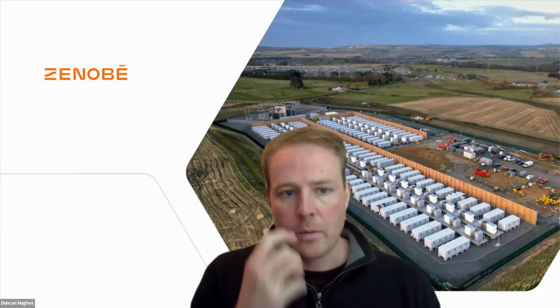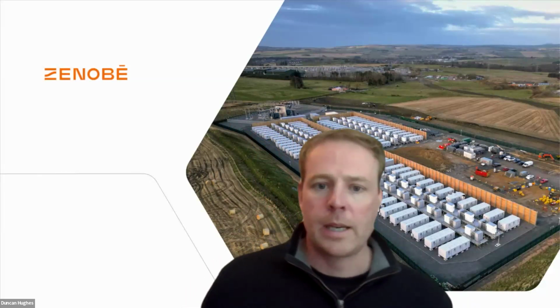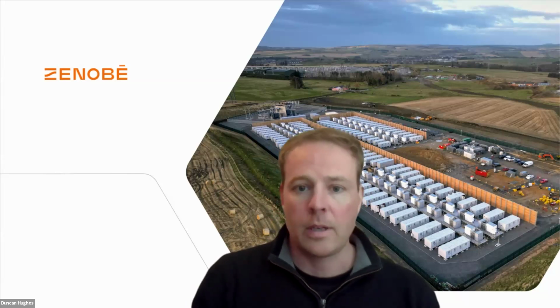You mentioned earlier, Scott, the Swiss Army knife type thing. So what we mean by that is at any one time, the battery system as a whole can be poised to provide a whole range of system services, whatever is needed by the grid at that point in time. So you might see, for example, a rocof event you mentioned, where the frequency changes very quickly. You will see an initial inertia response out of the battery to help arrest that frequency change. That will happen on the millisecond time scale. You will then start to see the next services come in, like the traditional frequency response services, responding to help the network recover as well.